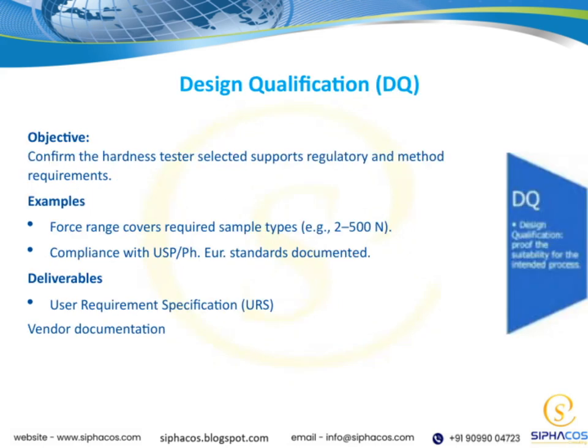Let's take a closer look at design qualification, or DQ, which is a crucial step in ensuring our hardness tester meets all necessary requirements. The main objective here is to confirm that the equipment we select actually supports both regulatory standards and our specific testing methods. For example, one key aspect is the force range of the tester. It needs to cover the sample types we plan to test, such as from 2 up to 500 newtons, to ensure versatility and accuracy. Another important point is compliance. We need to have documented proof that the tester adheres to recognized standards like USP and Ph. Eur., which are essential for regulatory approval and quality assurance.